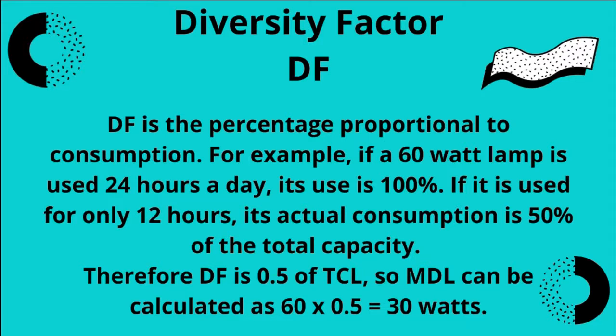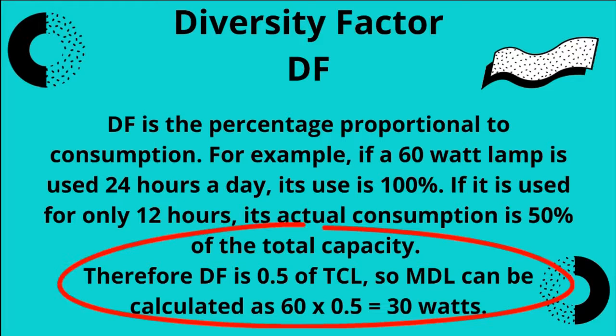For example, if a 60-watt lamp is used 24 hours a day, its use is 100%. If it is used for only 12 hours, its actual consumption is 50% of the total capacity. Therefore DF is 0.5 of TCL, so MDL can be calculated as 60 × 0.5 = 30 watts.